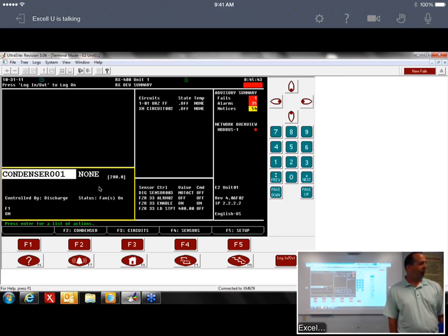One of the issues with case controllers is every time we come out with a new one, we change the network. I know that's a big pain in the butt, and it's certainly a pain in our butt too. CCB had the I/O network, and the problem with that was we were running out of addresses. There's only 256 devices you can address on an I/O net, and with all the different boards that we have, we had basically just run out of addresses.